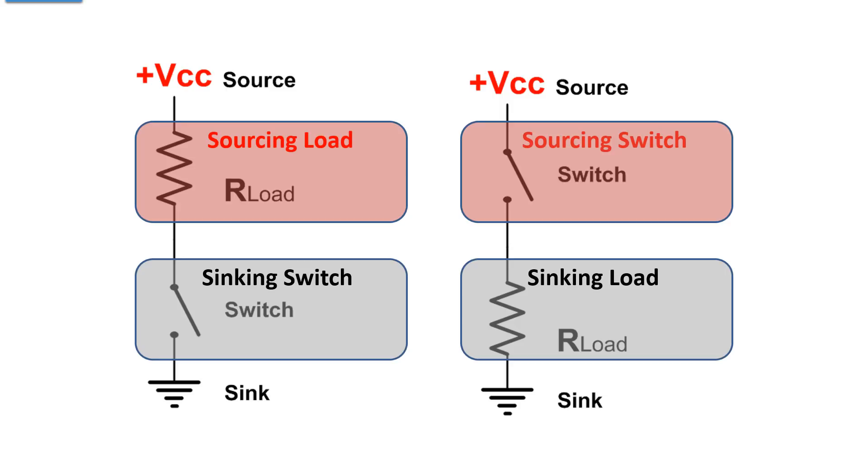Sourcing, sinking. You're probably looking at this comparison here and wondering what the big deal is and why it even matters. Remember that the control device in this illustration is a dry switch contact, not a solid state device such as a transistor. So in this case, that switch, same switch, can be used in either position as a sourcing input device or a sinking input.